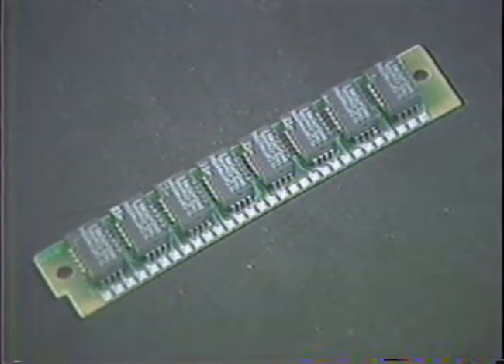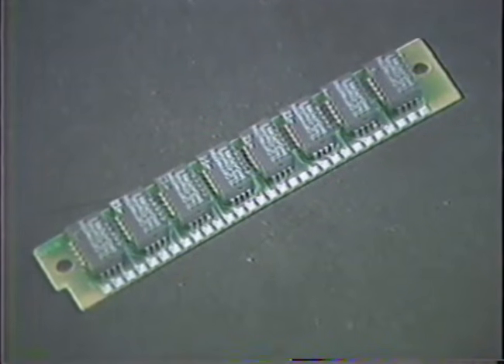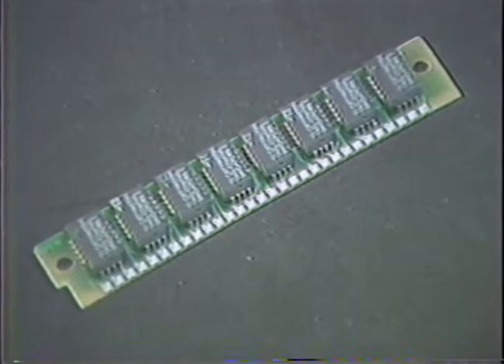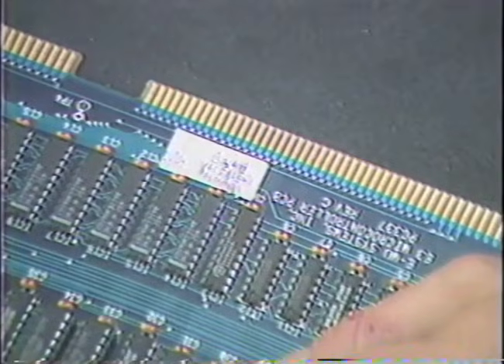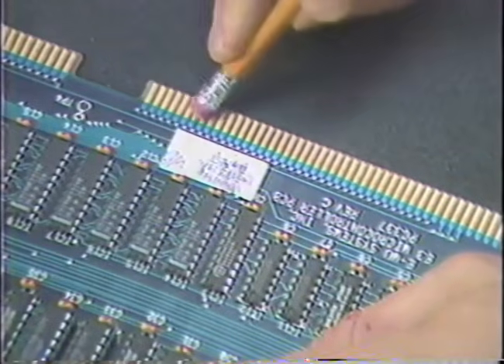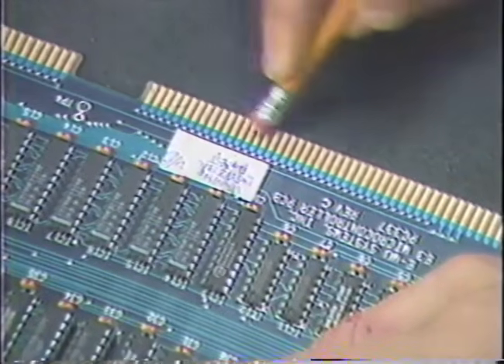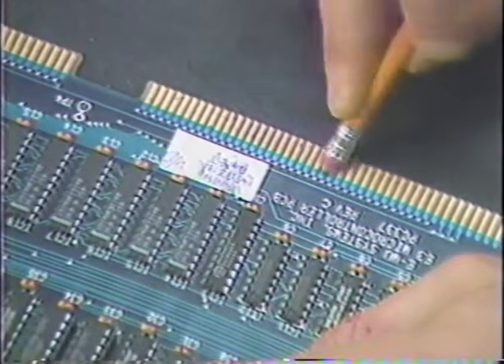If the E3 appears to boot, but the message "Can't load system" appears in the display, chances are that there is a memory problem. Remove the SIMMs, clean the fingers, and reseat them in their sockets on the microcontroller board. Be very careful when handling the SIMMs because they are very static sensitive. If this does not solve the problem, check the 8 latches carrying data and address lines to and from the SIMMs. Remove the PCBs and clean the gold fingers with a pencil eraser. The eraser will polish the gold, removing any contamination on the upper layer.